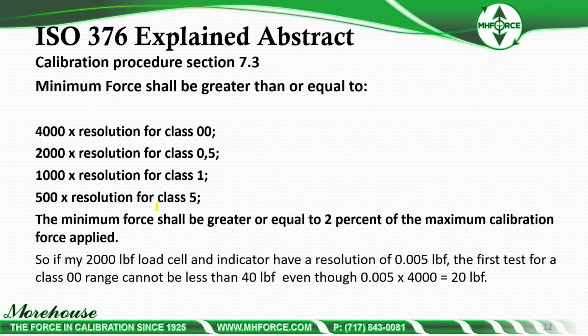The minimum force shall also be greater than or equal to 2% of the maximum calibration force applied. So if I have a 2,000-pound load cell and an indicator with a resolution of, let's say, 0.005 pounds, the first test for the class 00 range cannot be less than 40 pounds, which is 2%, even though 0.005 times 4,000 equals 20 pounds. This is something that's important. ISO says, hey, you're not going under 2%. ASTM has a recommendation that you can go under 2%. It's recommended that it be 2%, but you can go under. So ISO is basically saying nope on 2%. So you have these two criteria to use to determine the minimum force.